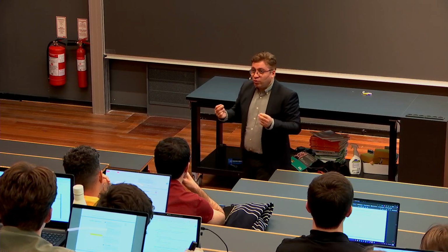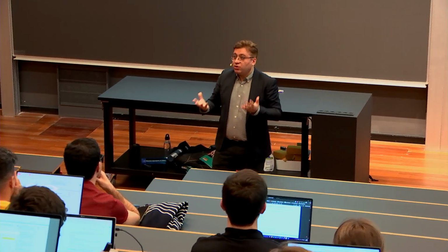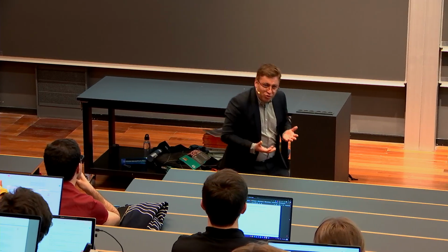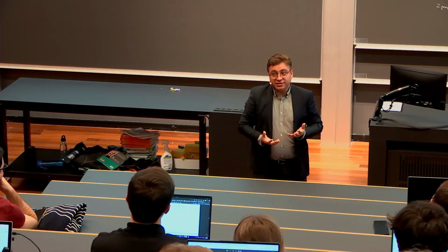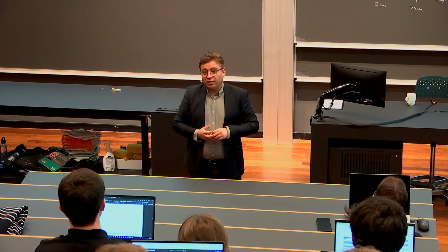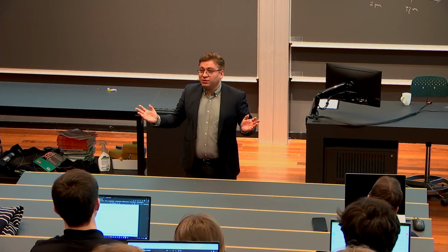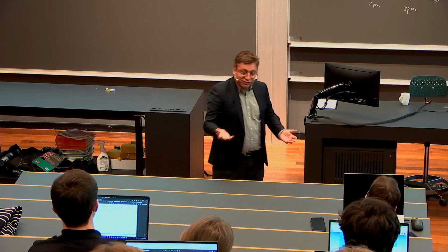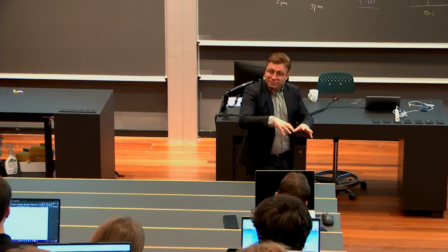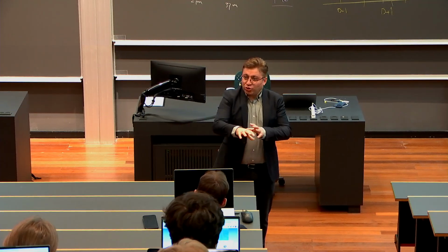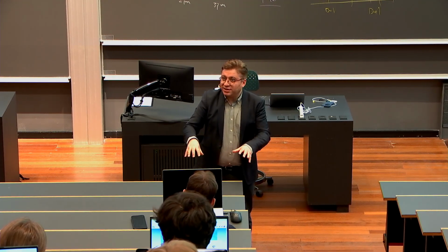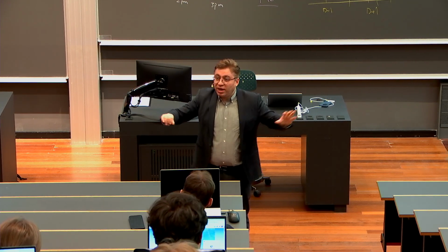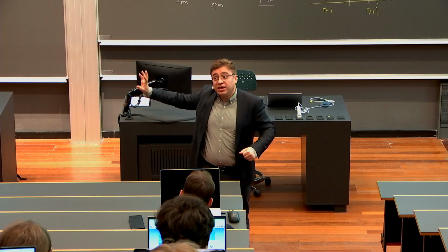So as a TSO, what you should analyze is the correlation of failures. For example, if you buy all your services from wind turbines, then you have a problem, I can tell you, because when the wind is not blowing, all the wind turbines will fail. But if you optimally buy, if you have some resource allocation, and you don't put all your eggs in the same basket, maybe you can say that, okay, when the wind is failing, maybe my EVs will help, maybe my heat pumps will help.